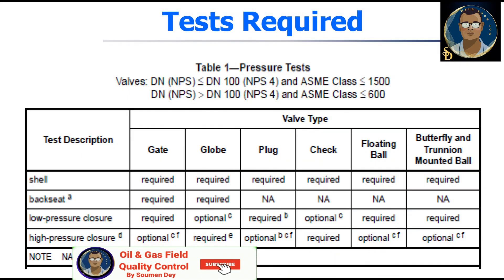As per API 598, you can see in Table 1 where the pressure test required or not required is clearly mentioned. For valve diameters less than 4 inch with ASME class less than 1500, and diameter DN more than 4 inch with ASME class less than or equal to 600, this table is applicable. You can see the back seat test is not required for plug valve, check valve, floating ball, and butterfly trunnion-mounted ball valves.